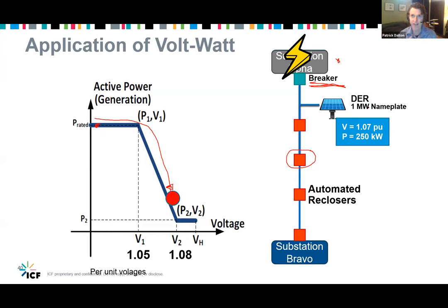It's sitting there, not activating most of the time, but if there is some sort of abnormal system condition, it's a backup to help protect customers on the system from experiencing overvoltage, which might damage their equipment. That's really why we're trying to keep voltage within ranges to start with: equipment manufacturers are expecting grid voltage to be within that range. They actually have a little bit wider range from the manufacturer's side, but it's based off of the utility range. So we need to be sure to keep voltage within that range so we don't damage customer equipment.